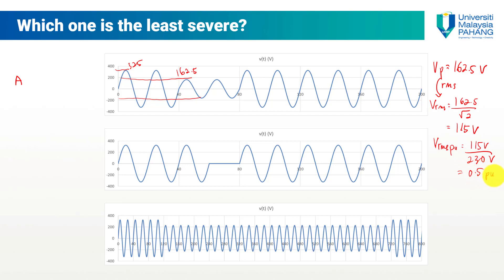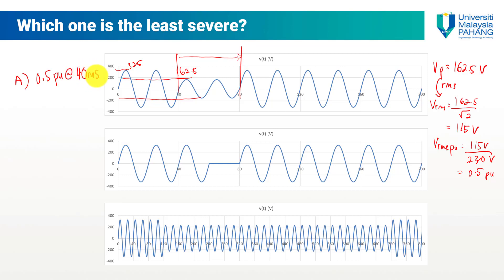For Event A, the RMS value is 115V. Converting to per unit by dividing by the base voltage of 230V, we get 0.5 pu. The duration of this waveform runs from 40 milliseconds to 80 milliseconds, so that's a duration of 40 milliseconds.